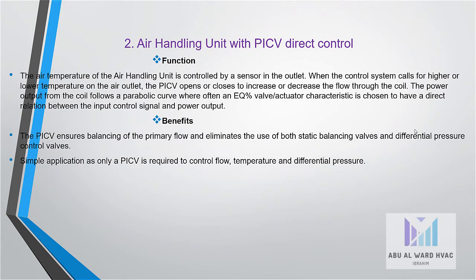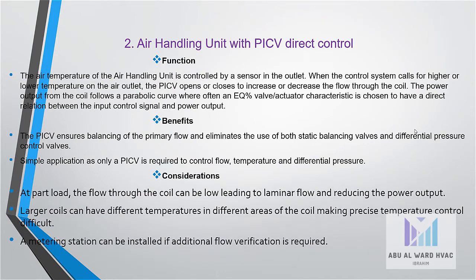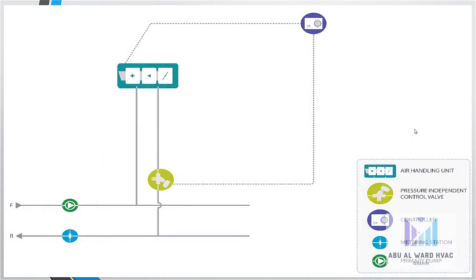The benefits: the PICV ensures balancing of primary flow and eliminates the use of both static balancing valves and differential pressure control valves. Simple application, as only a PICV is required to control flow, temperature, and differential pressure. Considerations: at part load, the flow through the coil can be low, leading to laminar flow and reducing the power output. Larger coil can have different temperatures in different areas of the coil, making precise temperature control difficult. A metering station can be installed if additional flow verification is required. And this is the schematic of this case.